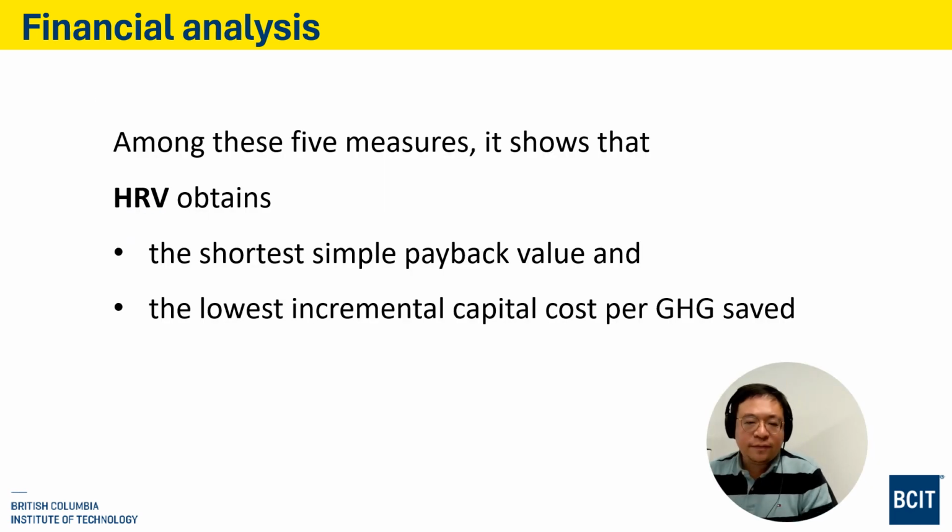So among these five measures, HRV shows the best result. It obtained the shortest simple payback value and also the lowest incremental capital cost per greenhouse gas saving.